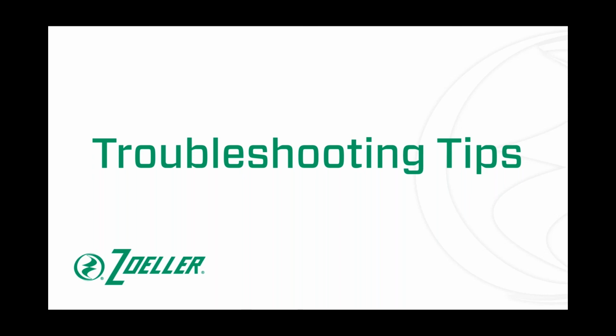Another troubleshooting tip: if you have a duplex system and a problem with one of the pumps, try switching the wiring in the control panel. Flip-flop the wires between pump 1 and pump 2. Physically hook up pump 2 where pump 1 was and pump 1 where pump 2 was. Try running the system again. This will help you determine for sure if you have a control panel problem or a pump problem. In troubleshooting, you have to determine the midway point in your system, cut it in half, and figure out which direction the problem is.